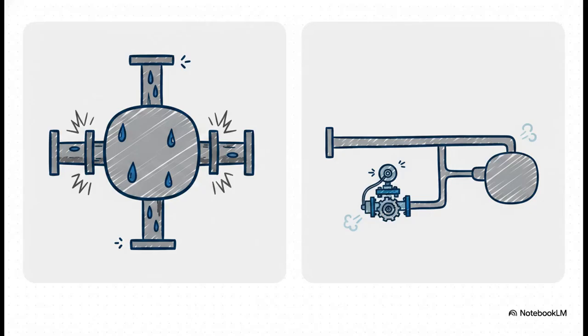Okay, so we know how it works and we know how it's powered, but how do you actually plumb a massive multi-ton tank of water into a giant hyperscale facility? Facility designers generally have to choose between two major piping methods, 4-port and 2-port. A 4-port or inline system means literally all of the facility's water flows through the tank at all times. The pro here? Excellent load absorption. It is incredibly stable. The con, though? Having to push all that water through a giant tank 24/7 causes constant pressure loss, meaning your pumps have to work way harder and burn way more electricity.